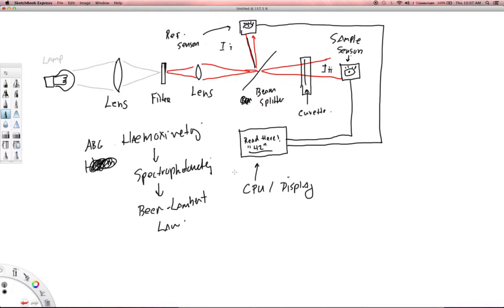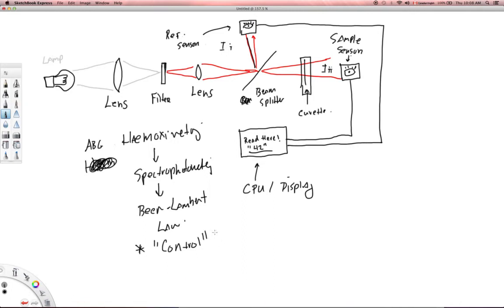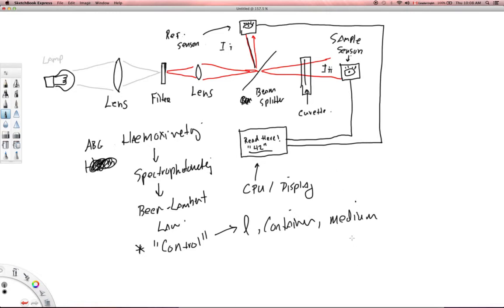Now, I do want to stress that for this whole thing to work, we need to be able to control for a whole lot of things. We need to be able to control the equipment, the cuvette, the length, the length of the pathway, how much blood is that light going through, what kind of container am I using, what kind of medium. If I were to use water, I may get a very different value, because this machine is designed to look at blood. That's what it's how it's calibrated, and so on and so forth. So I need to make sure that I'm using blood.